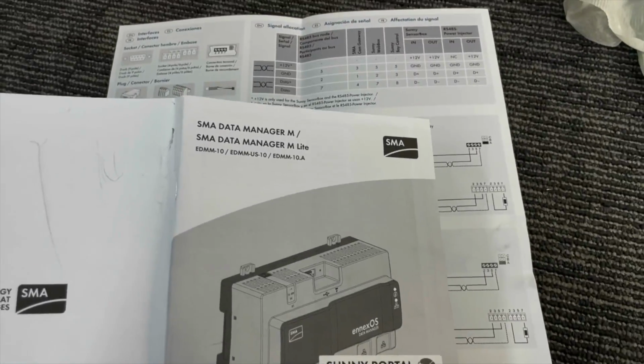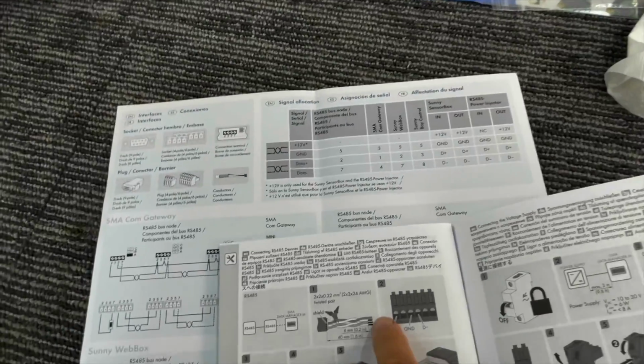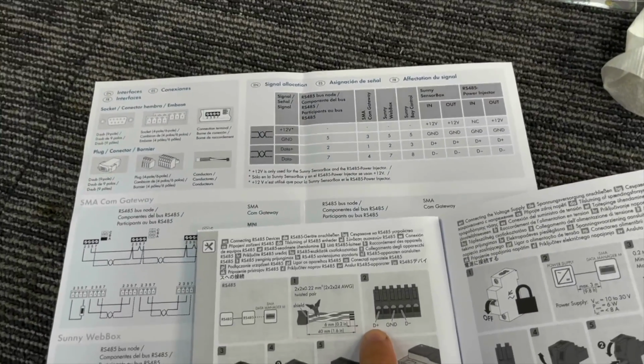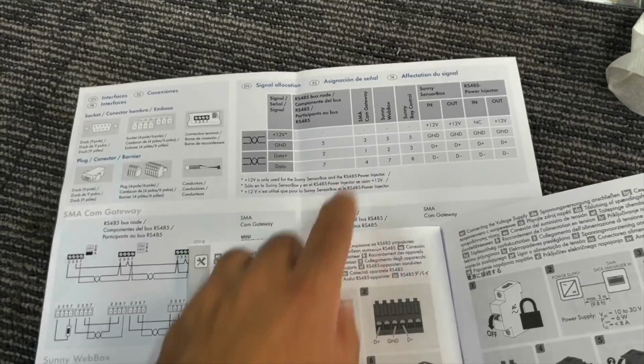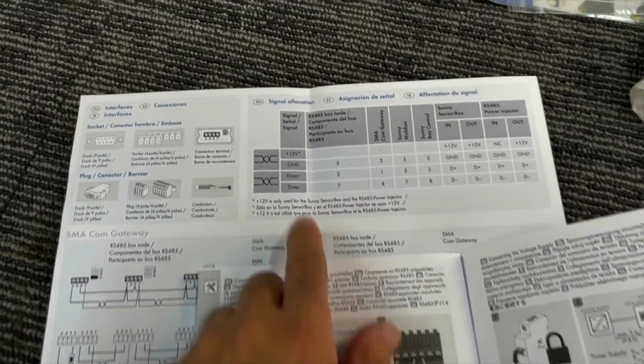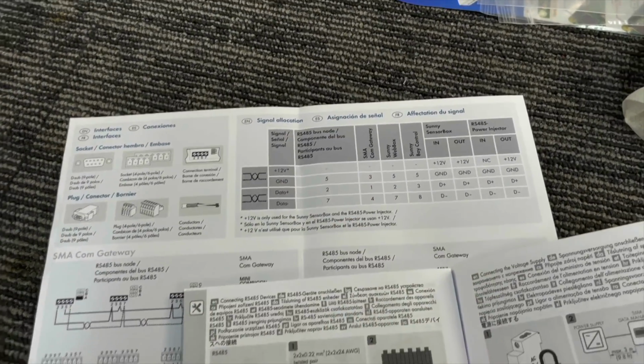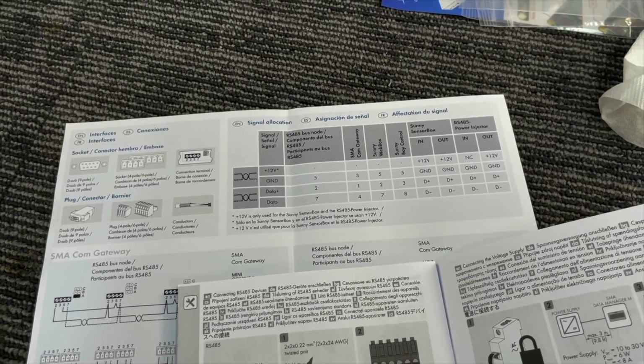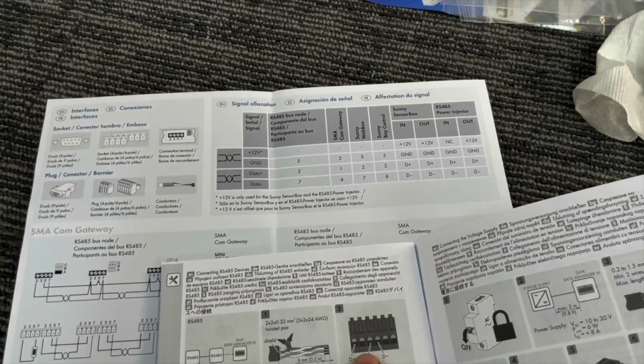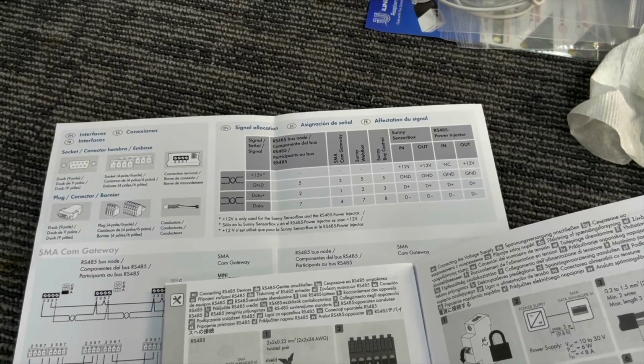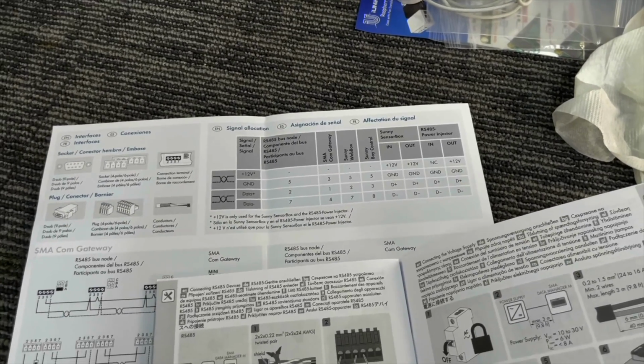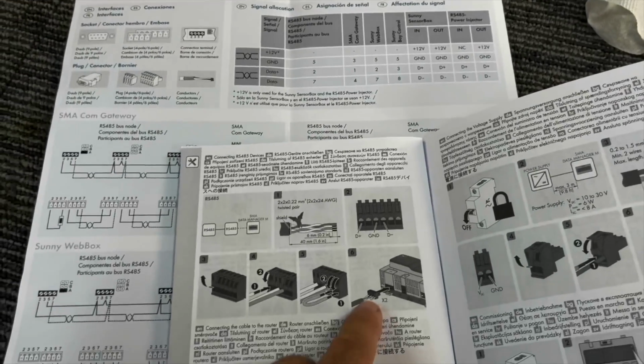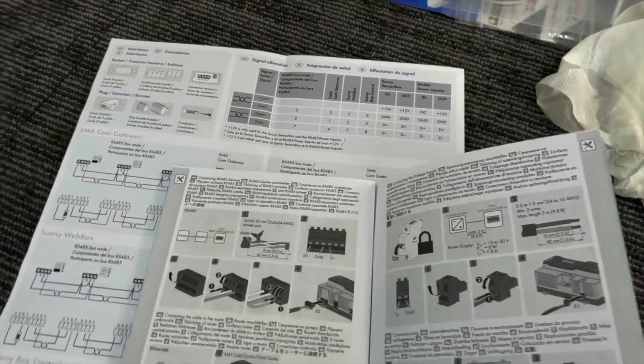This is the Sunny Portal Data Manager M manual, showing position 1 is data plus, position 3 is ground, and then 4 is data minus. So that's the connection we followed, and that's looking at the connector from the back as it plugs into the data manager. So just double checking that over here.